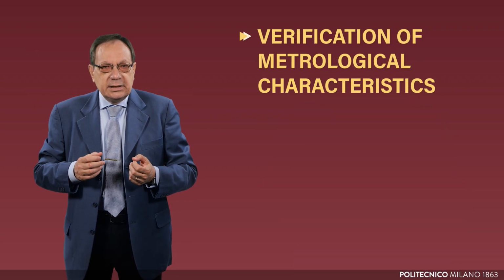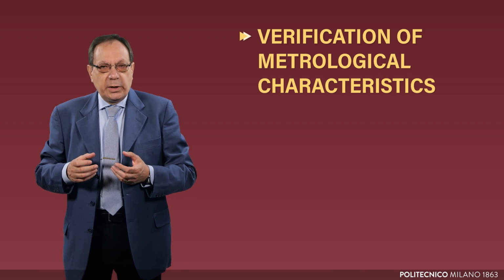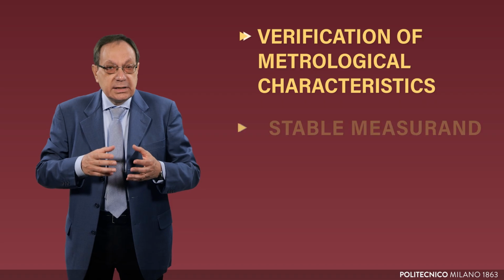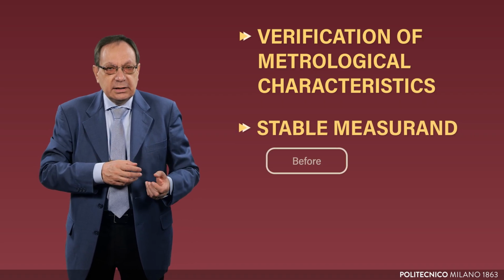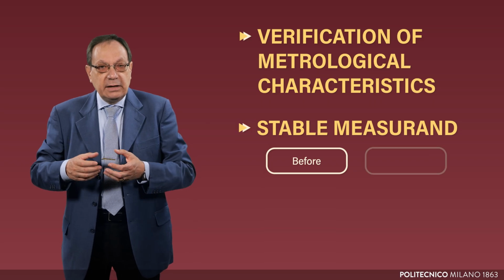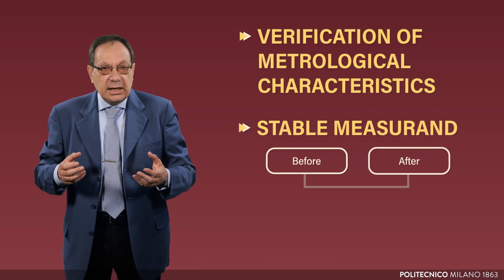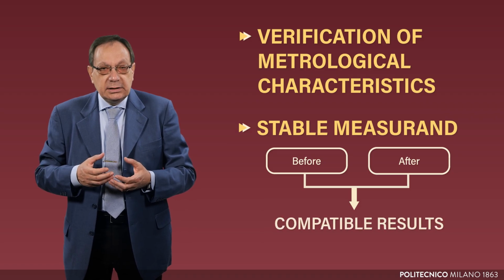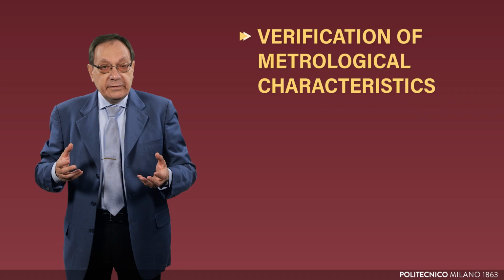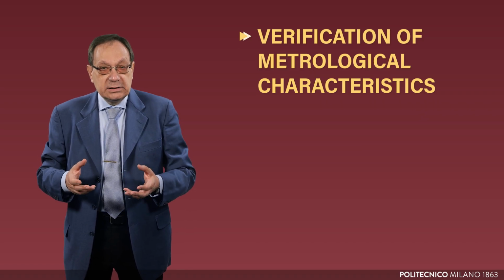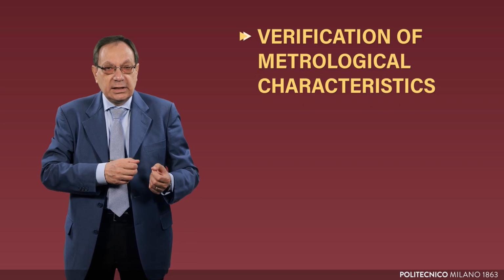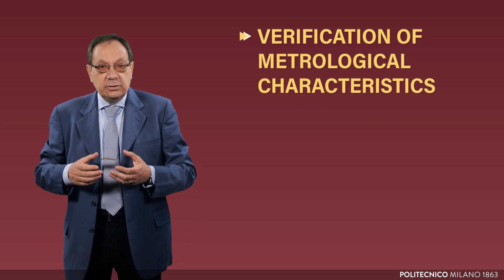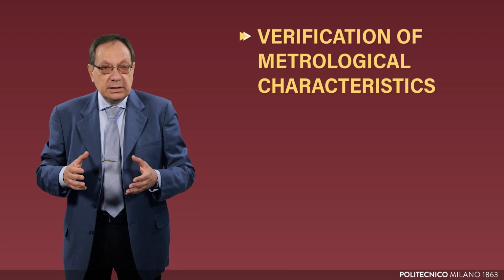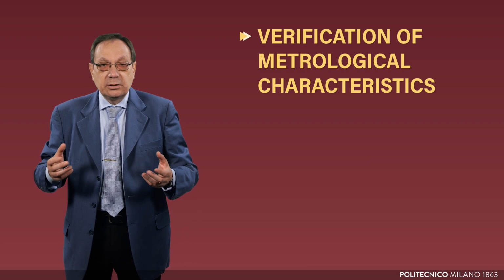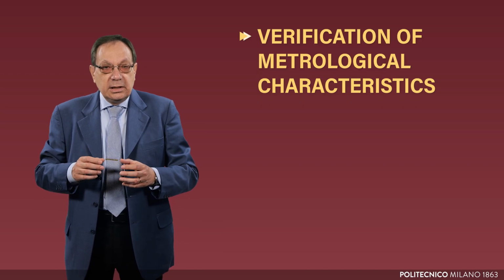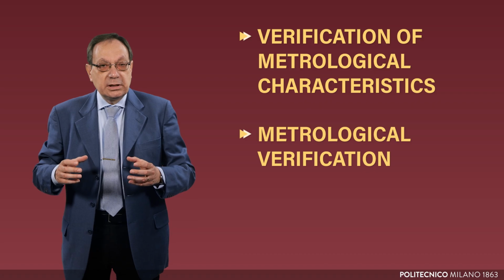Verification that the metrological characteristics are maintained can be carried out in various ways. For example, if you have a measurand that is stable over time, you can measure it before sending the instrument for calibration and measure it again after it returns from calibration. If the two results are metrologically compatible, the metrological characteristics are confirmed. If you do not have a measurand that is stable over time, but you do have an instrument with the same characteristics as the one sent for calibration and which has already been calibrated, you can measure the same measurand with both instruments. If the results are metrologically compatible, the metrological characteristics are confirmed. These procedures are usually referred to as metrological verification.